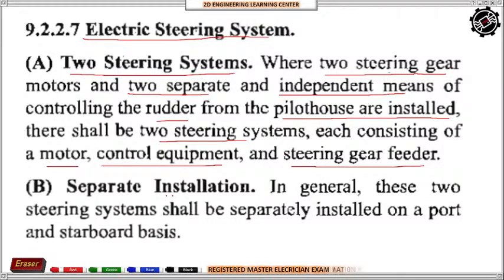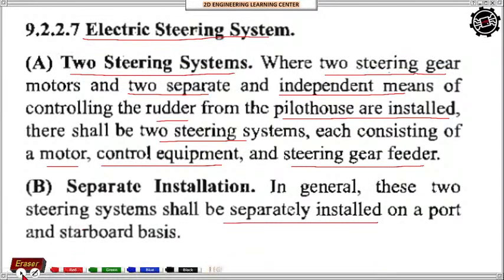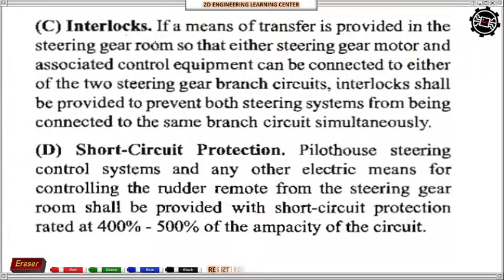So separate installation. In general, these two steering system shall be separately installed on a port and starboard side. So may sa left at sa right side ng ating ship, no? Port and starboard side. So interlocks, if a means of transfer is provided in the steering gear room so that either steering gear motor and associated control can be connected to either of the two steering gear branches, so interlock shall be provided.